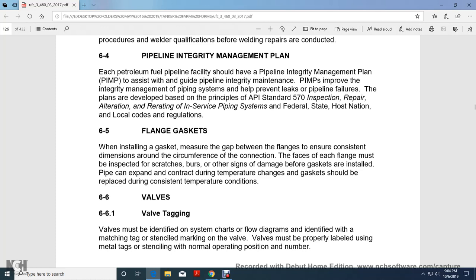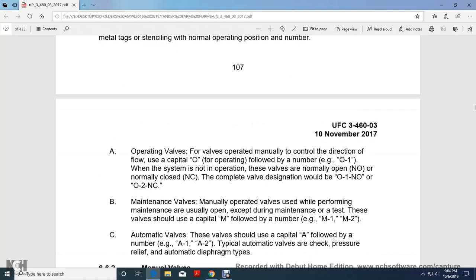6.6, valve tagging. Valves must be identified with the system chart of the flow diagram and identified with the matching tag with the stencil marking on the valve. The valves must be properly labeled. Use metal tags and stencils for the normal operating position number. For an operating valve to be operated manually to control the direction of flow, use a capital O for the operating valve with the number O1. If the system is not operating, the valve is designated normally open, NO, or normally closed, NC, completing the valve designation with O1 NO, O1 NC, or O2 NC.